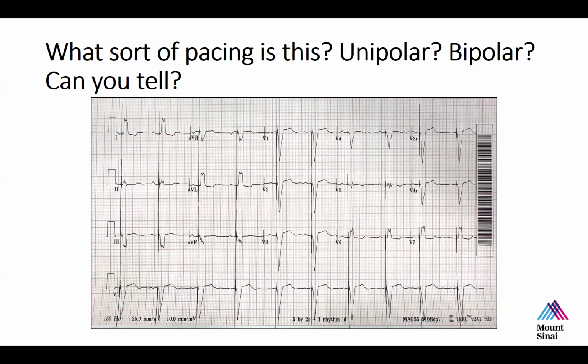So for example, when I was at Columbia, Dr. Quagabor, when he was still practicing, he felt that it was almost never going to be the case that his post-op patients were going to have heart blocks. So sometimes just so that he could say he put a wire in, he would put a single unipolar wire on the patient's heart, and that would be the only wire the patient had. Now, you can't pace through one wire that is a unipolar lead.